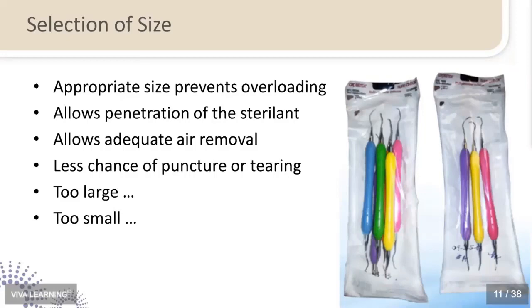Now, you're also seeing on the right-hand side of the screen an example of an appropriately loaded pouch. When you put instruments in, before you seal it, you should be able to put that pouch flat on the counter, and the instruments should line up side by side like soldiers in one single row. They shouldn't be stacked up on top of each other. So if they're side by side, you should have at least a 1/4 inch or a finger's width of clearance on either side of the outermost instruments, and you should have about an inch clearance from the top, or headspace, again, to allow for appropriate filling of the pouch with steam and for effective drying as well.